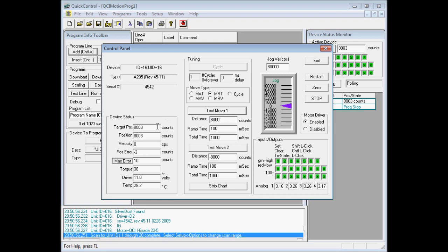As you can see, the target position is 8,000. The actual position is 8,003. There is a position error of three counts. Now the position error of three counts is due to our anti-hunt feature that prevents the motor from dithering or hunting to its exact position. As long as the position error is small and within error limits.